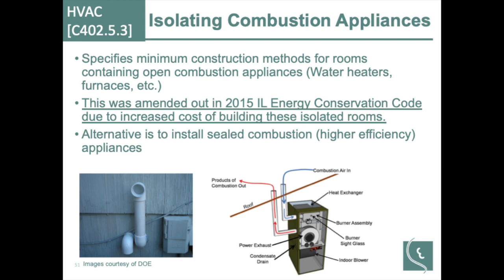Now this we don't have to do in the state of Illinois, but something to think about. If you're bringing outside air into that thermal envelope, this is going to be a potential weak point of a building system and potential malfunction. So that is one detail that we do call out. It is in the code, but Illinois has amended that piece out just due to the cost of constructing these thermally isolated rooms.